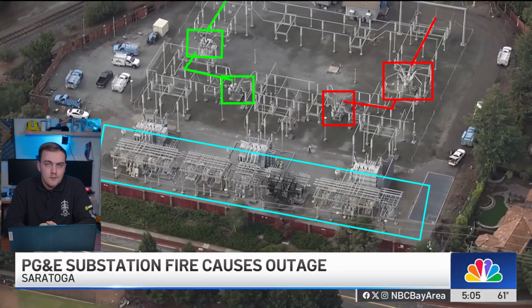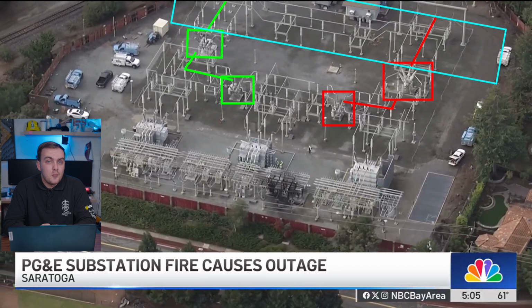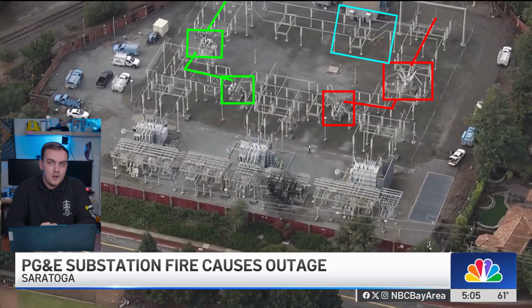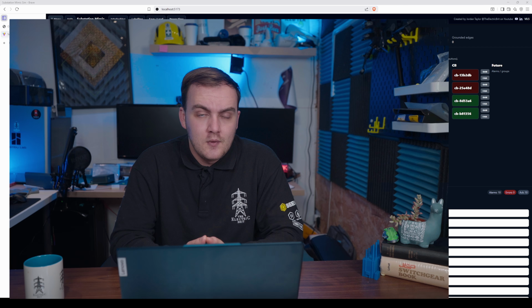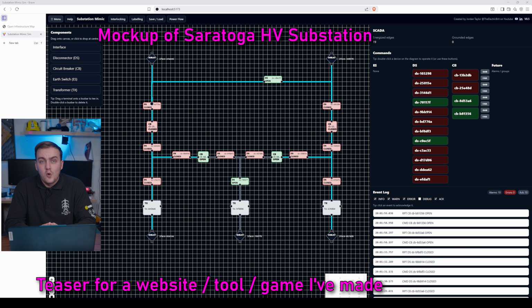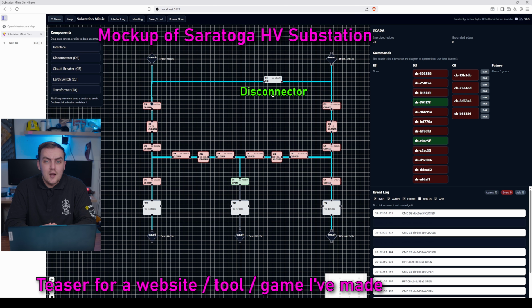And taking a look back at the top of the substation like I promised, we have this bus section of sorts that joins circuit 1 and 2 but doesn't have a circuit breaker. It only has this disconnector here which doesn't have the arc quenching abilities of a circuit breaker, and it moves much slower. So if you try to use this to break a live circuit, it will often turn into a puddle, which isn't great for long-term operations. But you can actually operate it live under one condition, that a parallel path exists for the load to flow down. So if all the other circuit breakers are closed, you can open this disconnector and it might spark a little bit, and it doesn't draw much of a meaningful arc with high energy.